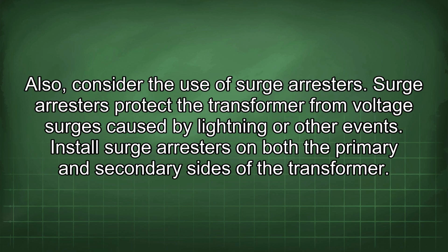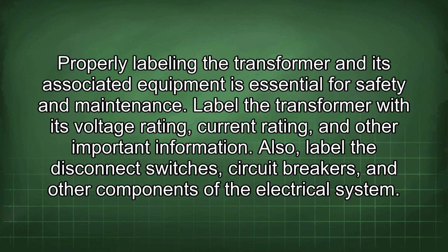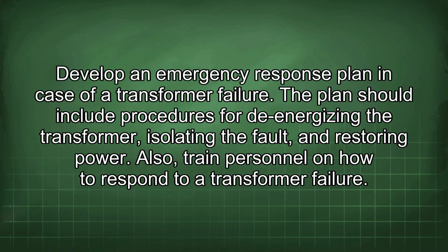Also, consider the use of surge arresters. Surge arresters protect the transformer from voltage surges caused by lightning or other events. Install surge arresters on both the primary and secondary sides of the transformer. Properly labeling the transformer and its associated equipment is essential for safety and maintenance. Label the transformer with its voltage rating, current rating, and other important information. Also, label the disconnect switches, circuit breakers, and other components of the electrical system. Develop an emergency response plan in case of a transformer failure. The plan should include procedures for de-energizing the transformer, isolating the fault, and restoring power. Also, train personnel on how to respond to a transformer failure.